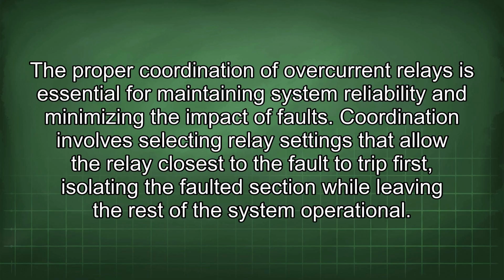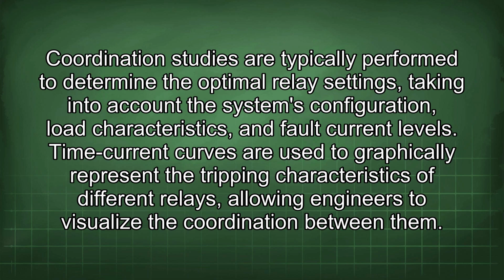Coordination involves selecting relay settings that allow the relay closest to the fault to trip first, isolating the faulted section while leaving the rest of the system operational. Coordination studies are typically performed to determine the optimal relay settings, taking into account the system's configuration, load characteristics, and fault current levels. Time current curves are used to graphically represent the tripping characteristics of different relays, allowing engineers to visualize the coordination between them.